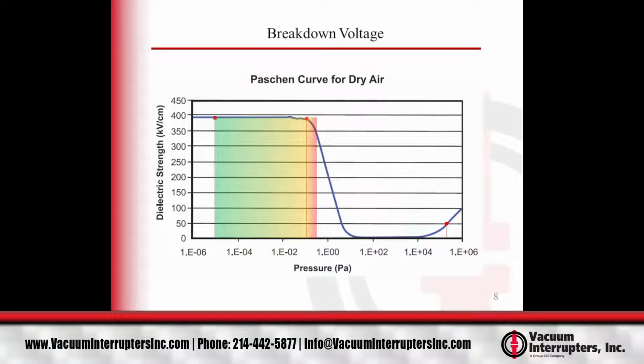For reference, this is what's called Paschen's curve. This is specific for dry air. So you see the dielectric strength, or the insulating ability, versus the pressure inside of the vacuum interrupter. On the far left side is very good vacuum, very low pressure. This is where vacuum interrupters start, at approximately somewhere around 10 to the minus 5 Pascal. Over their life, they increase in pressure, so they move to the right on this graph, eventually reaching a point somewhere around 10 to the minus 1 Pascal where the insulating ability drops off very rapidly.